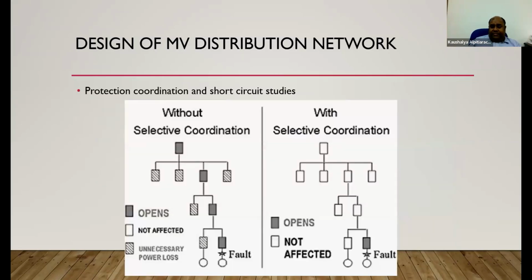Protection coordination. If you have protection coordination, it will sequentially trip during a fault. If not, sometimes the main circuit breaker would trip during a fault.